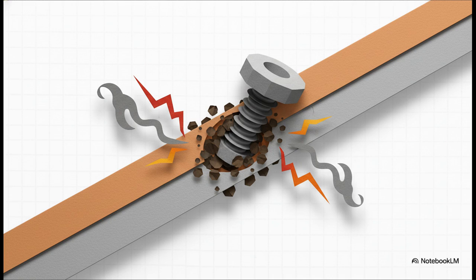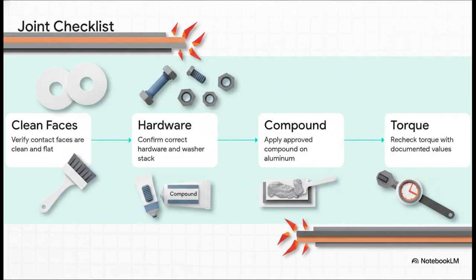Aluminum joints are particularly high maintenance here, as their oxide films form super fast and will just destroy the joint's conductivity if they aren't prepped right. Defeating this contact resistance takes strict discipline through a really practical pre-delivery checklist. Step 1, you've got to verify the contact faces are completely flat and clean. Step 2, confirm you're using the correct hardware and washer stack. Step 3, apply an approved joint compound on those demanding aluminum interfaces. And finally, Step 4, recheck the torque using documented, tested manufacturer values. Stable pressure keeps resistance low. Unstable pressure creates heat. Simple as that.